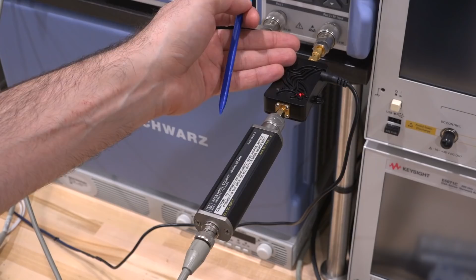And of course, the ZNL comes with a full-fledged noise figure measurement capability as well. And here is the tab for that. And if you go under Overview, it has the same nice signal flow diagram for noise figure measurements too. It tells you what the instrument is doing during calibration. It tells you what the instrument is doing during measurement. So you can do direct measurement or an offset IF measurement or whatever noise figure you want to do.